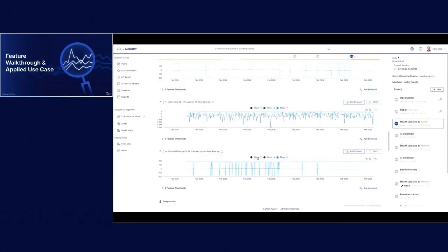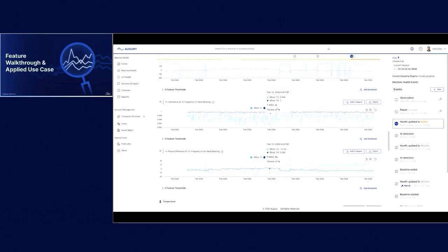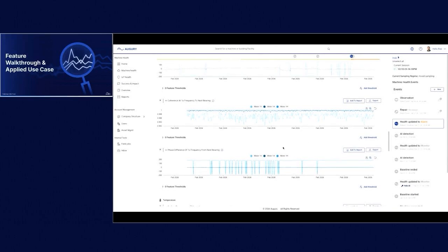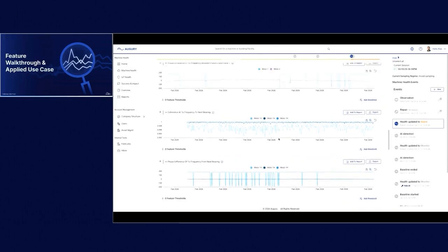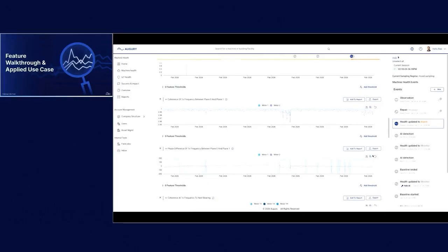We don't have enough data here in this particular case to kind of troubleshoot further because we just have this sort of new here. We are seeing some movement in that 180 degrees across that motor itself. So just seeing that kind of shift rocking itself back and forth. Whereas again, for our vertical and our axial, these are closer to that 0 degrees, right? Plus or minus about 10 to 20. Which means that these are both working, moving as one unit across the machine. So these are the types of data we'll be seeing. Again, wish I had a more pretty example here, but this is the idea here as far as the multiple channel phase. And then with our single channel phase, we have had this longer.